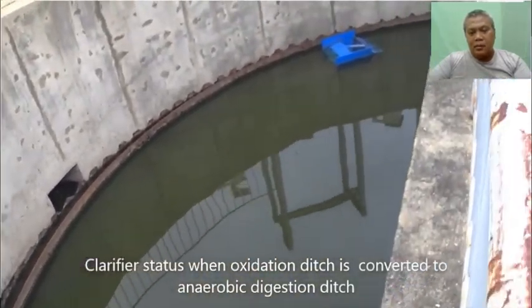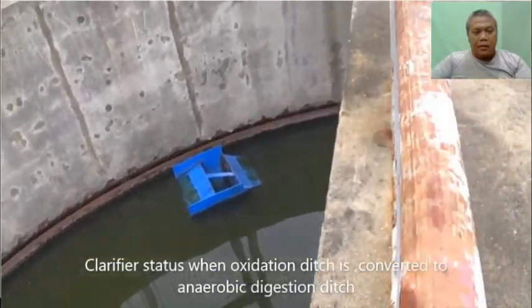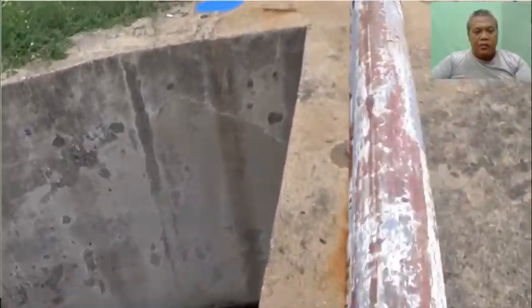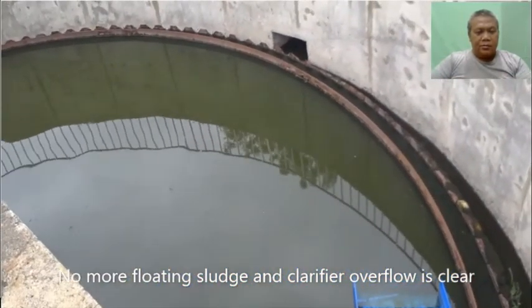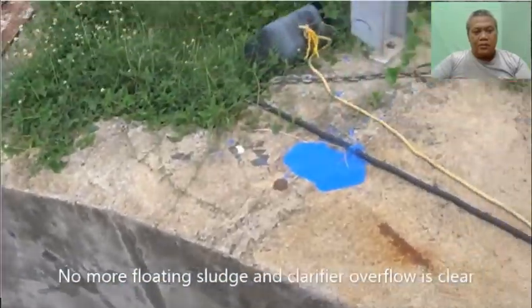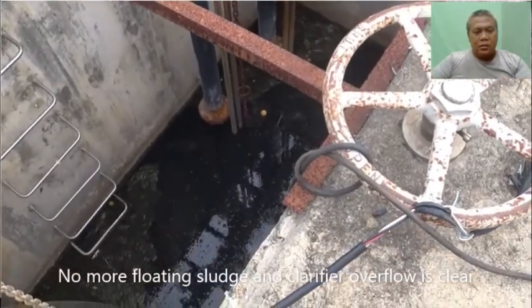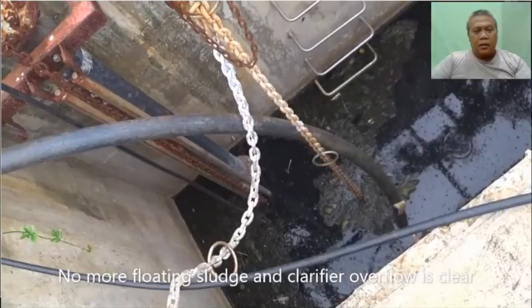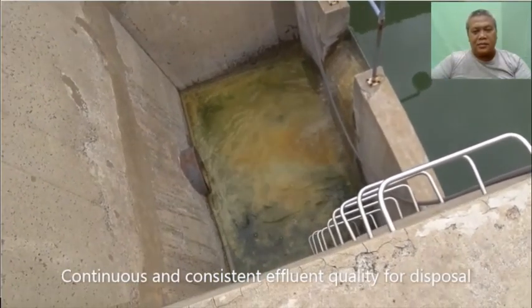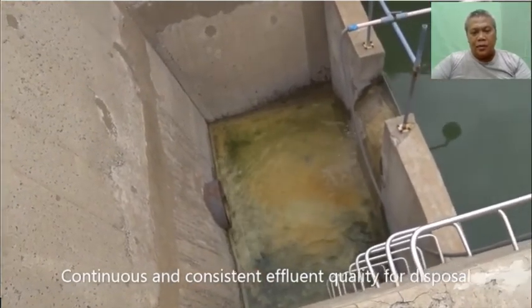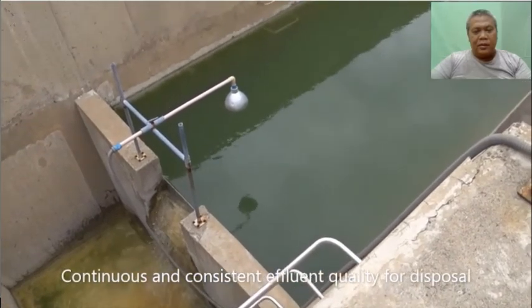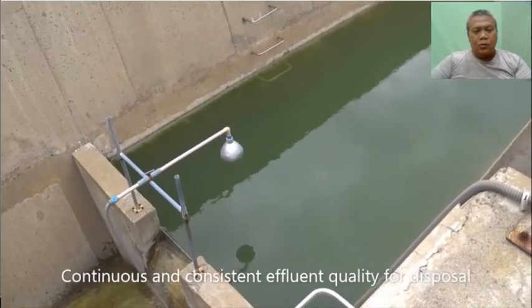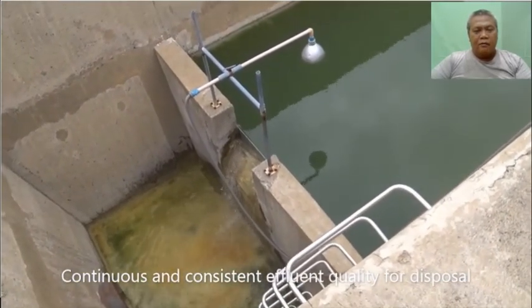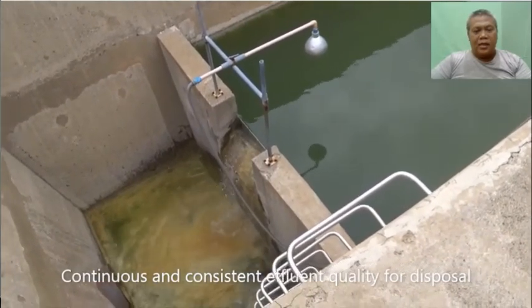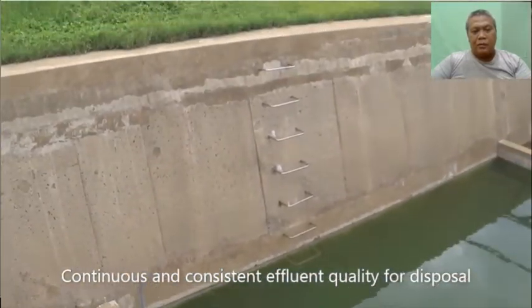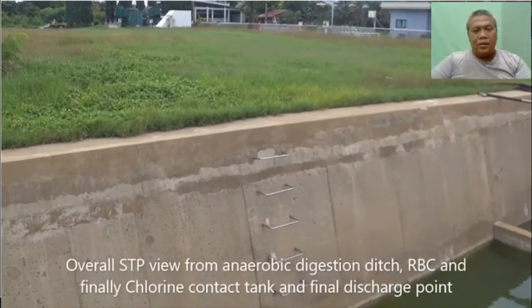This is already the clarifier that is receiving wastewater coming from the RBC. Here you can see that there is no floating sludge. This is the sludge tank or the sludge return of the oxidation ditch. And finally, this is the effluent wastewater that is continuous and consistent in its effluent quality, and the analysis of this effluent water shows a marked reduction in ammonia and phosphate. In fact, there are times that the phosphate already passes the standard and that ammonia is also closing in.